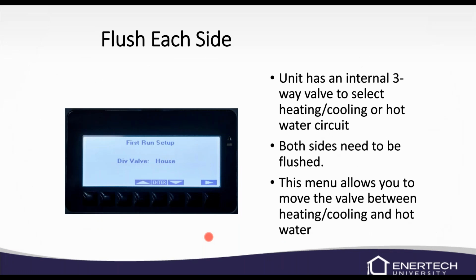So we're going to have to flush each side. So when we get to this, where the diverting valve is in the house position, or the hydronic heating side of things, if you press up or down arrows here, you can highlight that house. Once that house is highlighted, you can press enter, and it'll start to flash, and then you can change it to hot water, and it'll switch that valve over, and you can flush the hot water circuit.